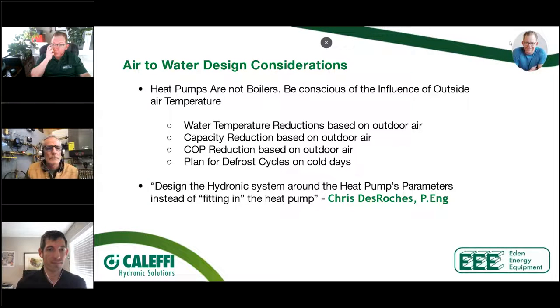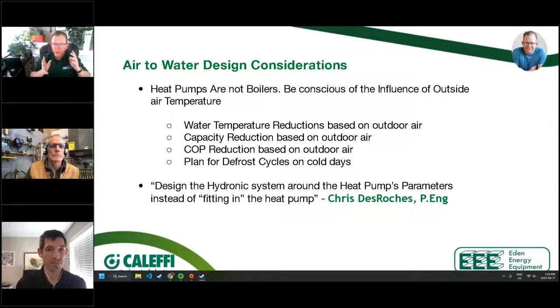So as we move along here, some things that we have to pay attention to as we talk about air to water design, or frankly, hydronic heat pump design, that plays into what Max is saying: if we put this into a leaky house, traditionally we'd go with a boiler, and the smallest boiler you can buy is typically about 100,000 BTUs. And in most houses, including older homes, at 100,000 BTUs, you're not going to have any problem heating that house. So the rules of thumb where you hold three fingers up and it covers the house and you go, it's a 3-ton, or all these crazy methods they use, we can't do that anymore.